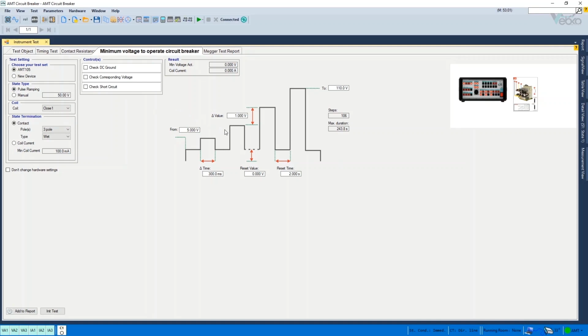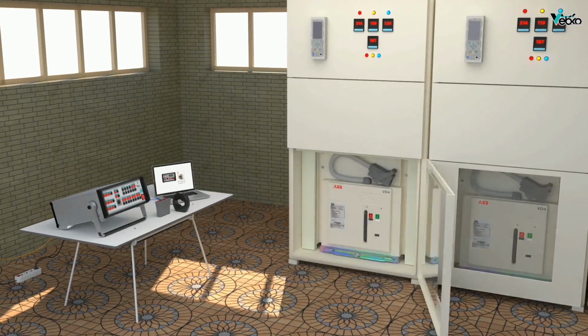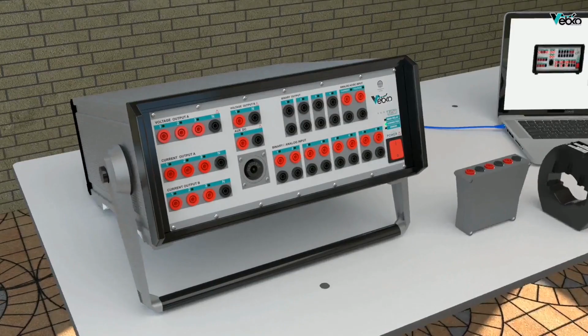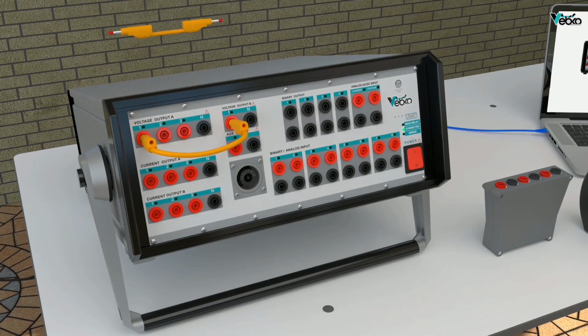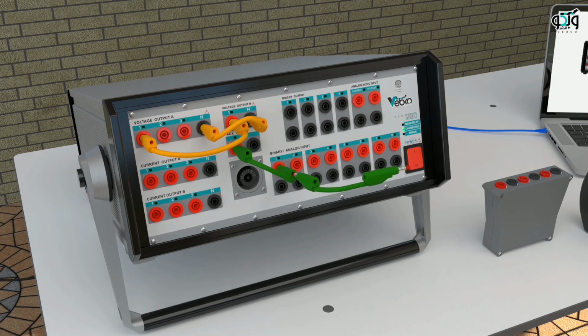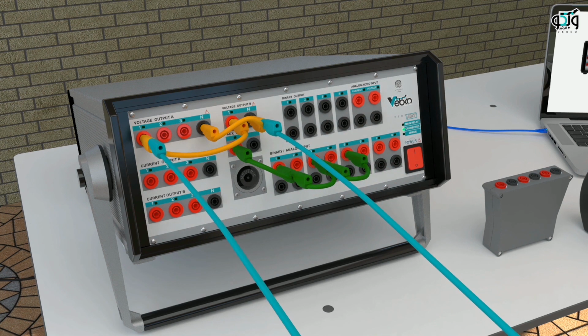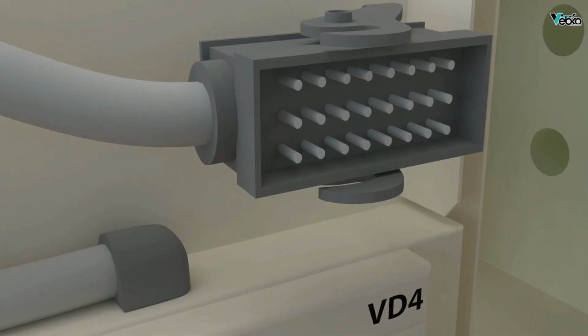In this example, the voltage is increased from 35 to 80 volts with 0.5 volt steps, and each step takes 0.5 seconds. The value for reset voltage is 5 volts and its application time is considered to be 0.5 seconds. After specifying these factors, the wiring is done according to the guide available in the picture. In this wiring, first the two voltage sources are paralleled in order to use the maximum current of the device, and then they are connected to the control coil to apply the fed voltage. Afterwards, in accordance with the number of contacts selected, L1, L2, and L3 contacts are connected to binary inputs to record the operation of the circuit breaker.